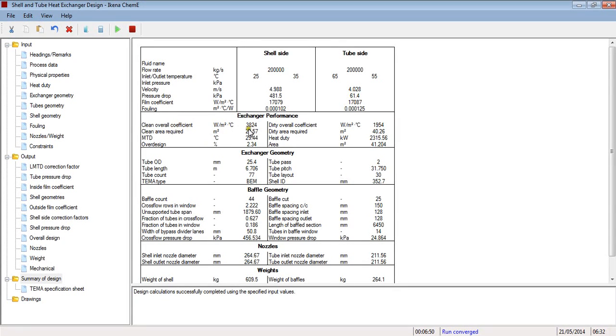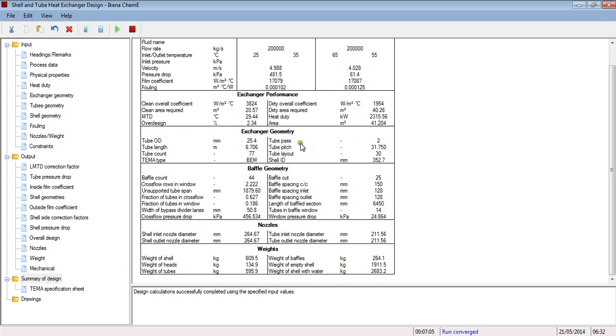And as you will have noticed, the heat transfer coefficient increased. Same for the fouling heat transfer coefficient, that has increased as well. The tube counts have reduced. Shell ID has reduced slightly, and our overdesign is 2.34%. You have all the information in here. On the summary, you have weight of the heat exchanger and things like that.